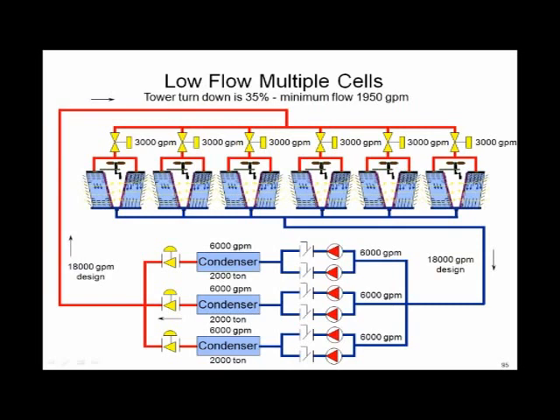But anyhow, long story short, he's working with low flow multiple towers. He gets a phone call and he goes out and takes a look at this plant. What does he see? Well, the owner says, I cannot maintain 85-degree water even when I'm only running one chiller with your towers. Now, look at this. You've got a minimum turn down of 35%. That means the minimum flow rate to any one of these cells is 1,950 GPM. Design is 3,000, but the minimum is 1,950 for them to work. You've got 3 chillers, 2,000 tons each, 6,000 GPM each.